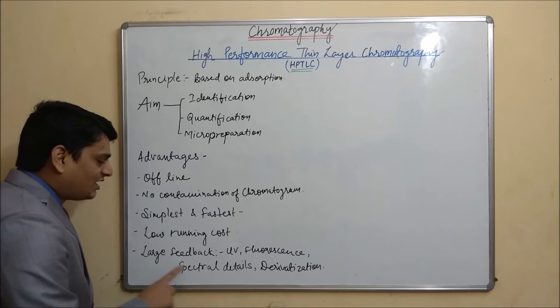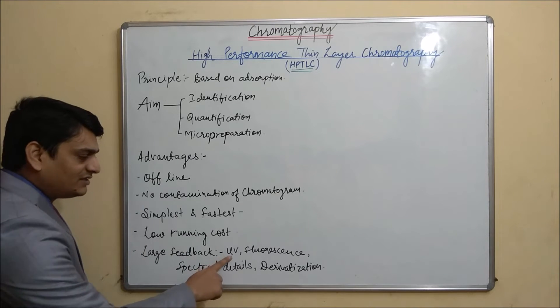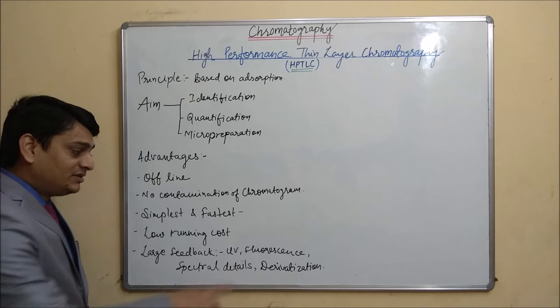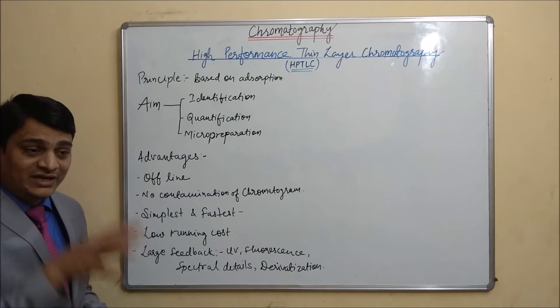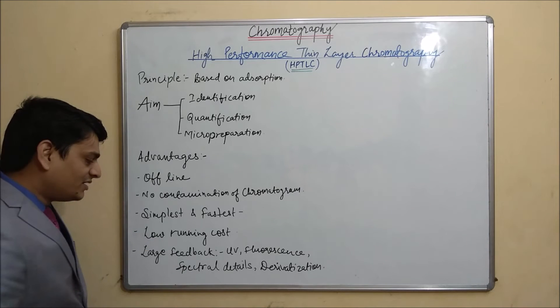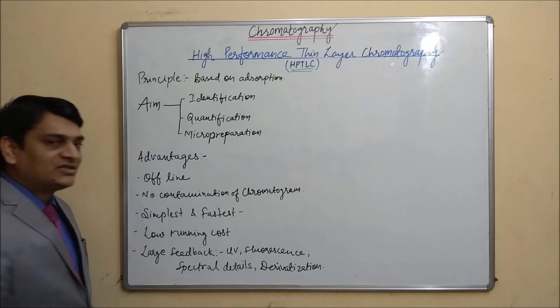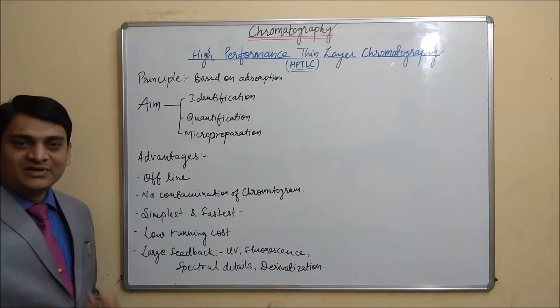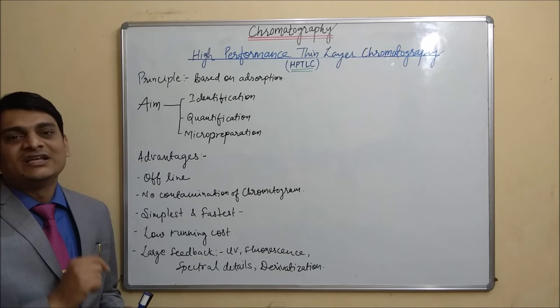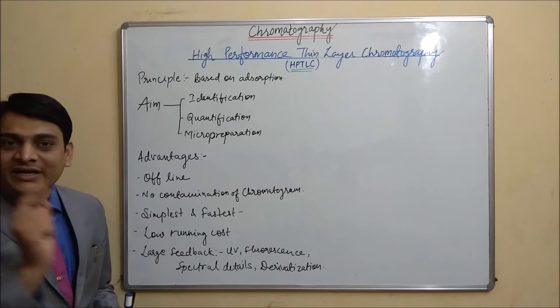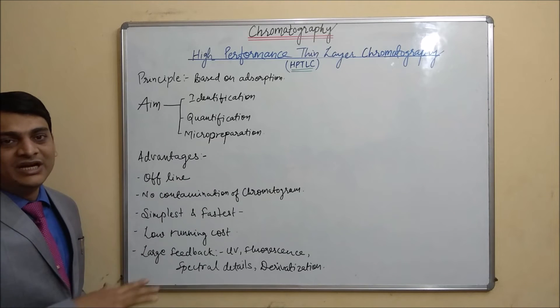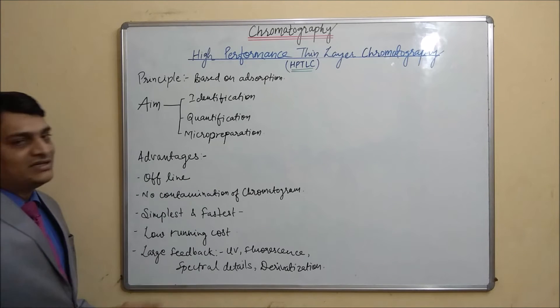The next advantage is large feedback. The HPTLC scanner uses a UV lamp to detect compounds, and it can also detect compounds based on fluorescence. UV and fluorescence detection systems are already present in the HPTLC scanner. Additionally, the HPTLC scanner provides spectral details — it gives the UV spectrum for that particular detected spot.